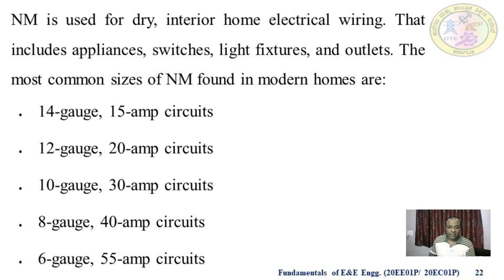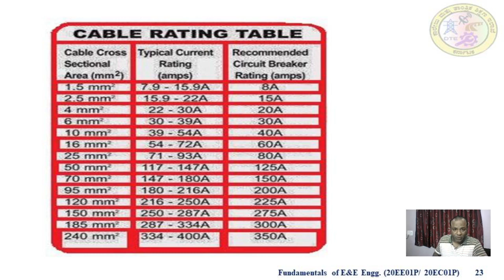For example, 1.5 mm square is used for a typical current rating of 7.9 to 15.9 ampere. The recommended circuit breaker rating is 8 ampere. Here the circuit breaker rating is also given, and the current rating is also given for different types of wires. And see another one, 2.5 mm square. The current rating for that is 15.9 ampere to 22 ampere, and the circuit breaker used for that is 15 amps. Like that, 10 to 15 wires are given, having different sizes, different current ratings and different circuit breakers used for them. You can refer to that list.